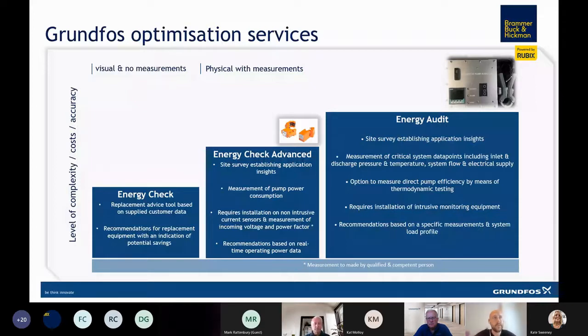We've done this many times over the years where customers said a pump gets shut off on the weekend, so we don't need to account for it. Then we measure the absorbed power and find whoever was supposed to turn it off on Friday didn't, so the pump had been running all weekend for no reason.